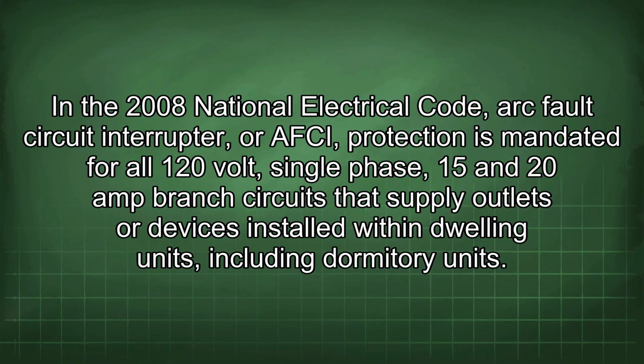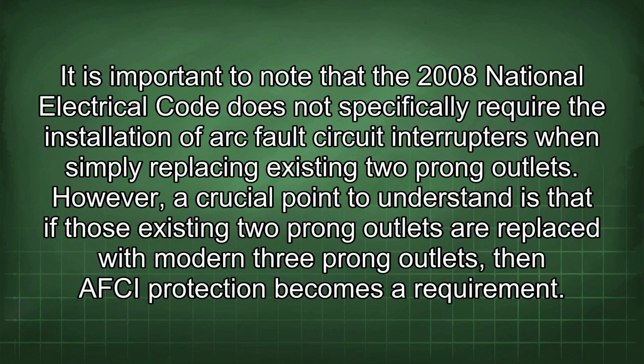In the 2008 National Electrical Code, arc fault circuit interrupter, or AFCI, protection is mandated for all 120-volt single-phase, 15 and 20-amp branch circuits that supply outlets or devices installed within dwelling units, including dormitory units. It is important to note that the 2008 National Electrical Code does not specifically require the installation of arc fault circuit interrupters when simply replacing existing two-prong outlets.